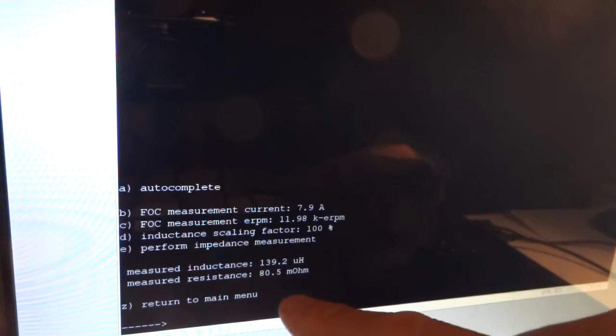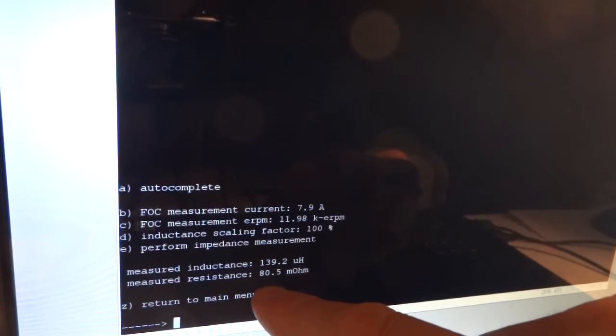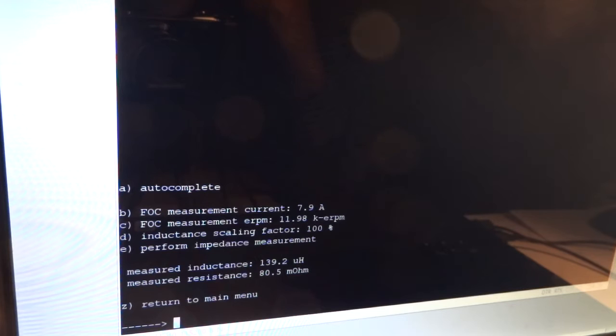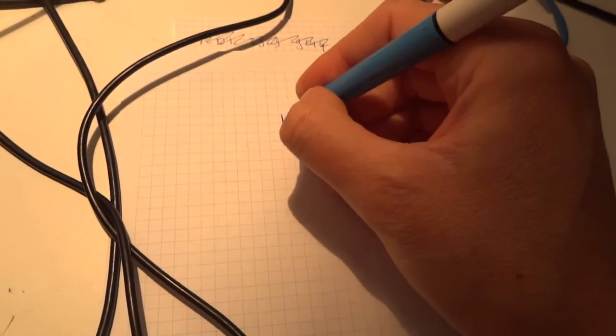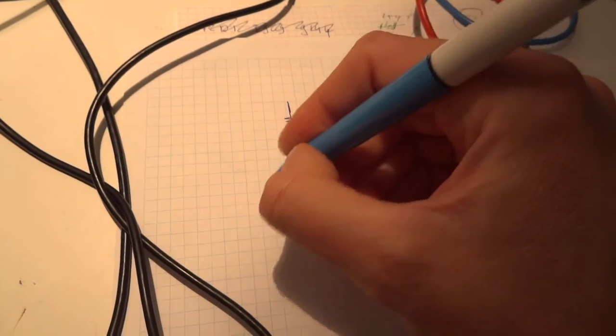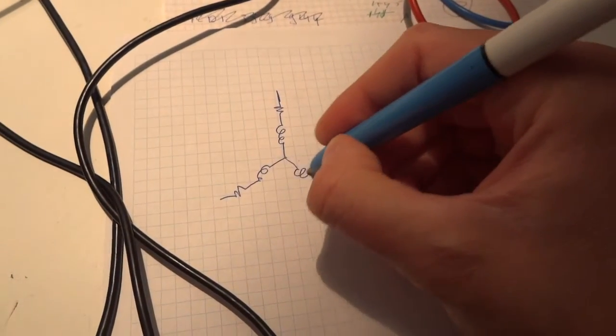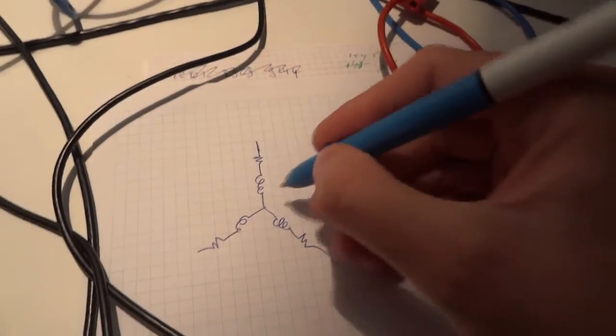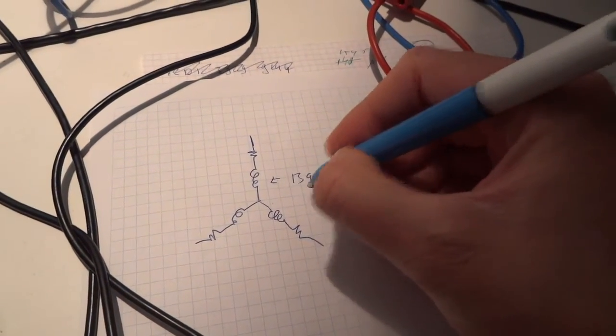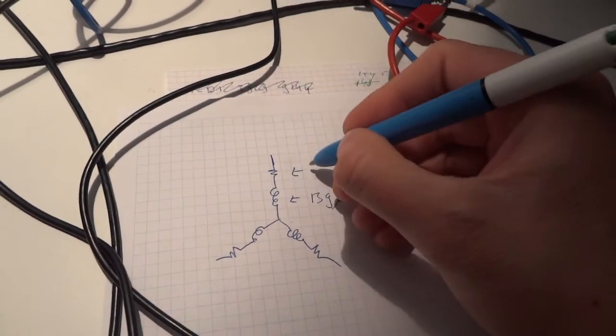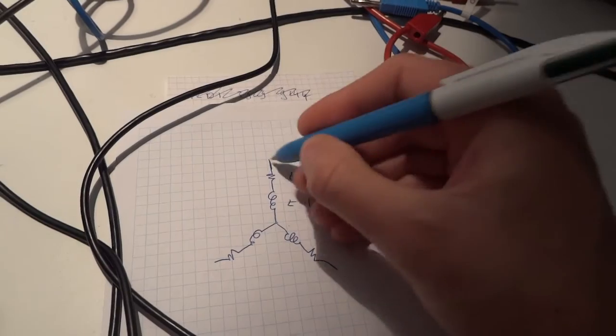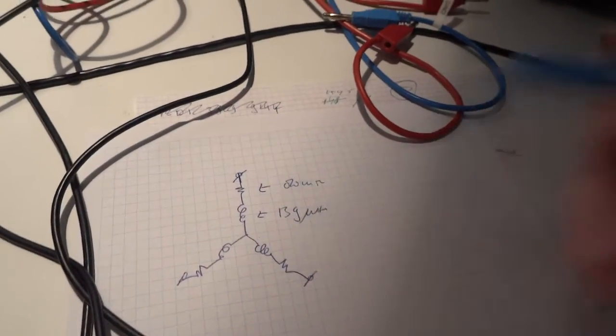It makes a noise during this measurement. See, there was no overflow, and it saw 140 microhenry and 80 milliohm. About these values, these are for when you have a motor, when you draw it in star configuration. So with this particular setup, this one is 139 microhenry and this one is 80 milliohm. And then these are your 3 motor terminals.